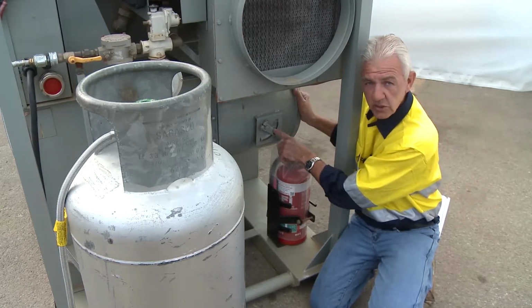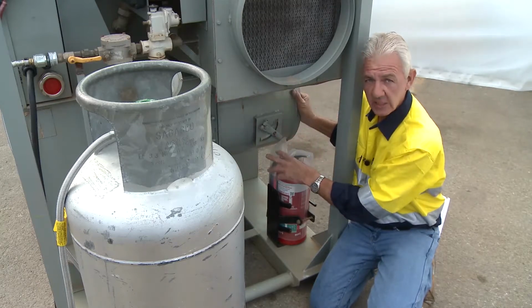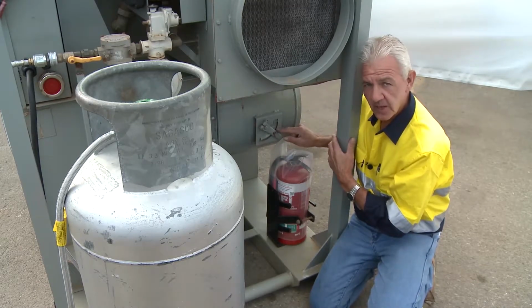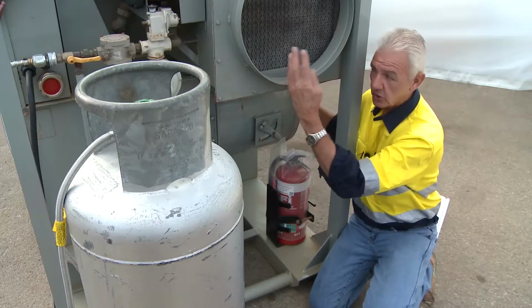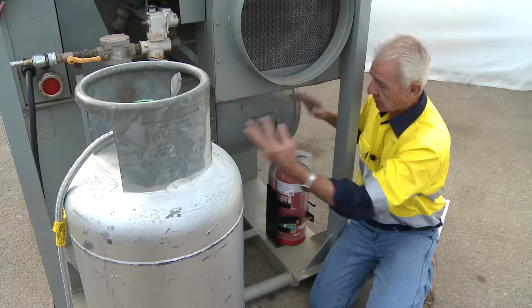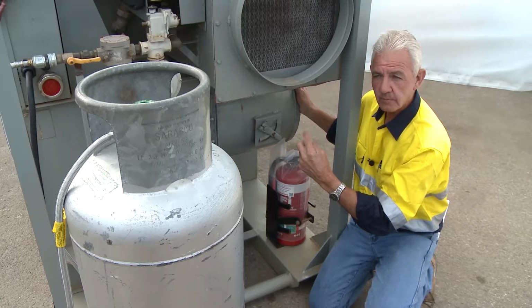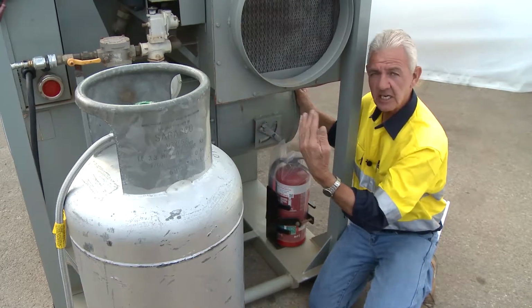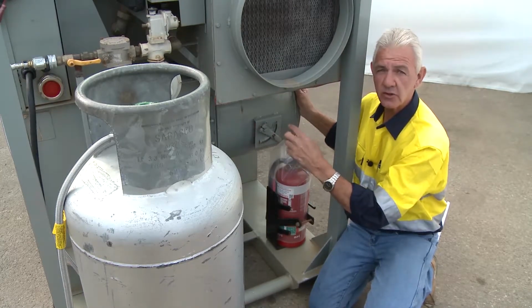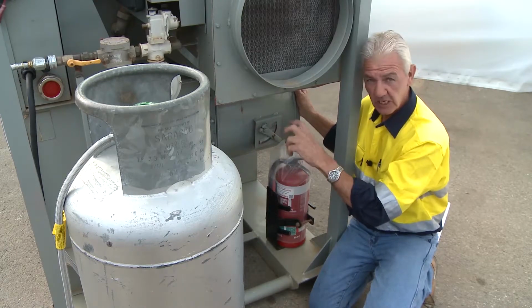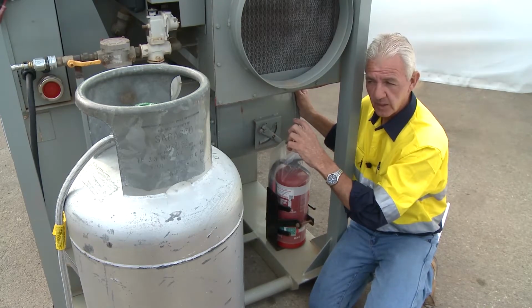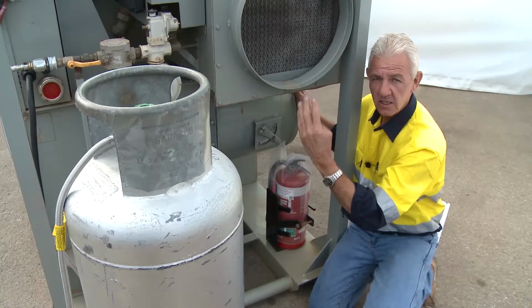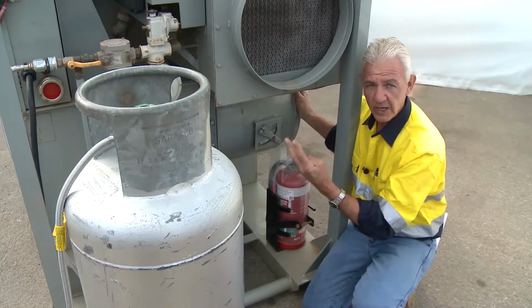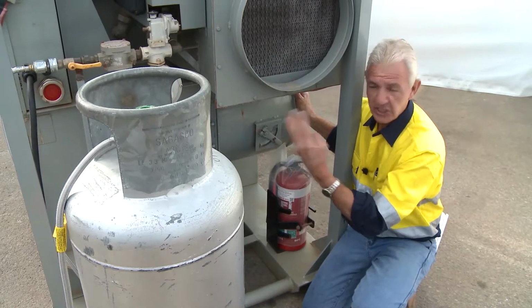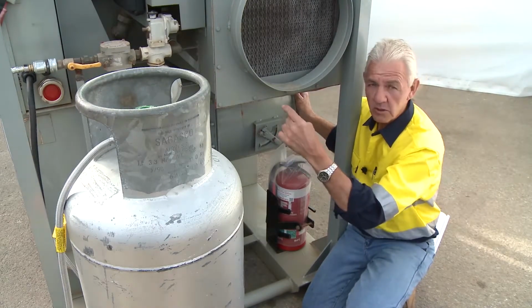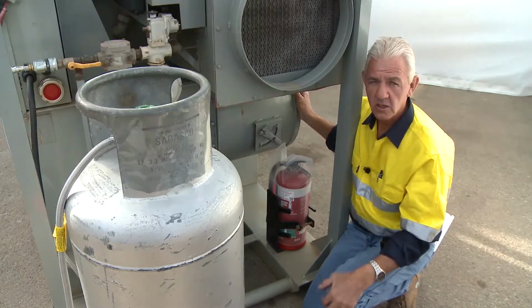But now we begin to make sense of what that magnehelic gauge was up there. This damper gives me the opportunity to control the magnehelic gauge, or the airflow that's coming through here. So the magnehelic gauge gives me an indication of where I need to be in relation to the standard operational procedure for this particular piece of equipment. What I need to do is have it on 1 to 1.5.